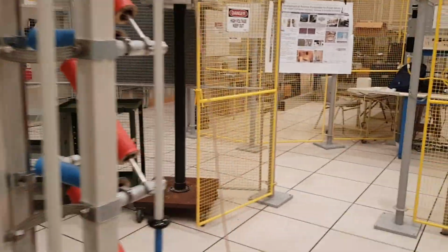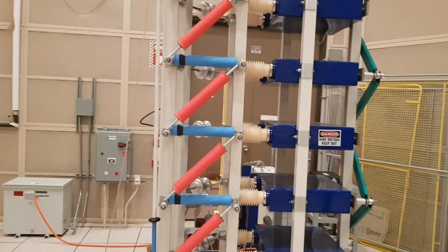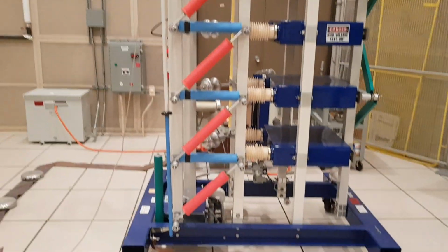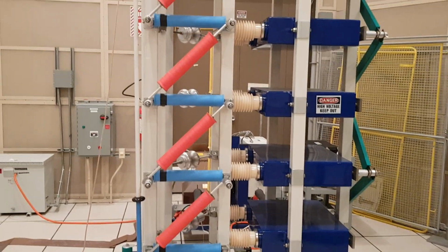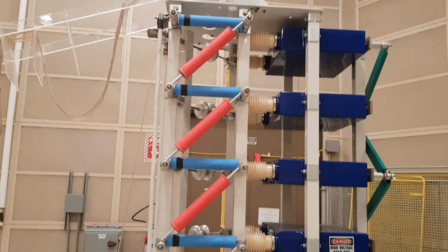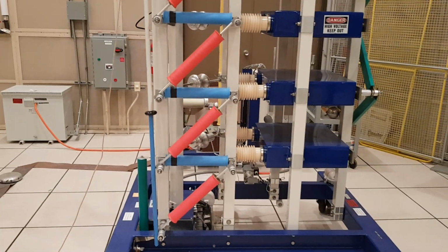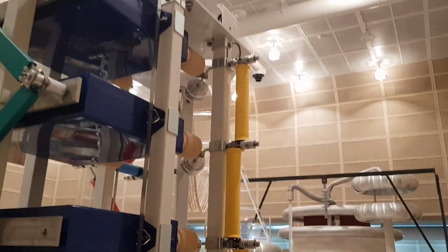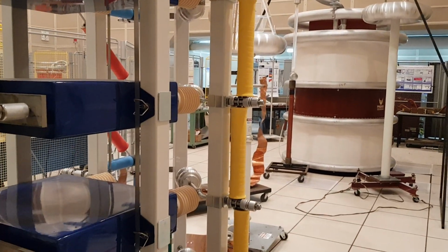Now, here come the two resistors that we use basically to decide the rise and the fall time of the impulse generator. So the blue ones are basically your R1, which is responsible for the rise time, and your red resistors are basically R2, which is responsible for the fall time. And then finally here we have these yellow resistors that we have to make sure that the voltage is uniform across each layer of the impulse generator.